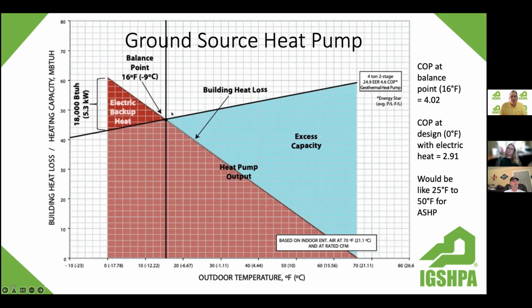And our balance point now goes from 31 degrees with an air source heat pump down to 16 degrees. So you can see this triangle is significantly smaller, and only about 5.3 kW of backup heat needed with this two-stage unit. This is an Energy Star 24.9 EER unit, two-stage, 4-ton. So I try to compare apples to apples here as far as equipment components go. So the difference is 13 kW to 5 kW, really. Some variable speed geothermal heat pumps could even eliminate this. Likewise, there are some variable speed air source heat pumps, but we do have still some capacity degradation as the outdoor temperature gets a lot colder.